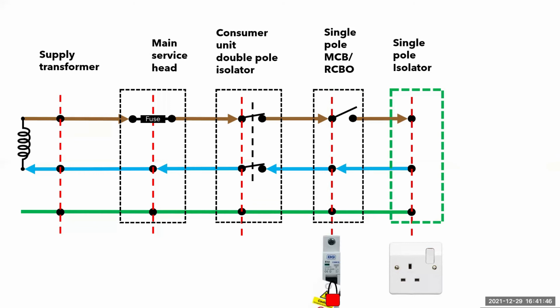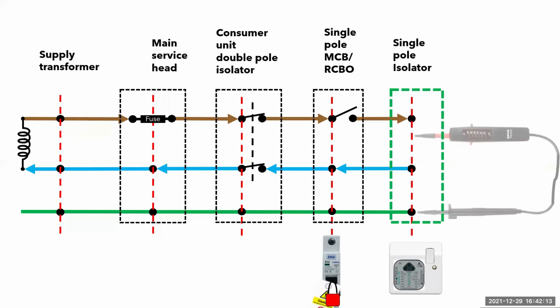We can initially test the socket front by plugging in a socket tester as a further check to increase our chances of success before we gain access to the live terminals inside the socket. I recommend buying a socket tester where all the LEDs light up, or it has a self-test, so that you know if one of the LEDs is malfunctioning. Once you are 100% satisfied that you can safely gain entry to live parts, only then can you unscrew the faceplate to test at the terminals with your GS38 approved voltage indicator.